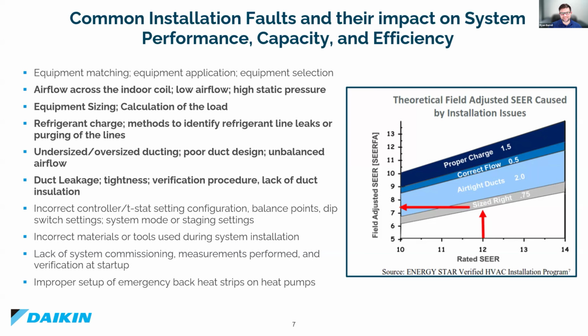But it's kind of that situation where they tell you to use UL 181 listed tape. Well, if you try to use UL 181 red letter tape in a 130-degree attic and you happen to sweat a lot like I do, then that stuff does not stick very well. It's a flex to sheet metal to anything. And so something like foil tape, which is what we don't want to use, happens to stick. So there are a lot of situations where you just have to understand that installers are doing the best with what they have, and they have no intent. They didn't wake up that morning to do something wrong, and if anything, it might just be a lack of information. So I put all these common installation faults. I don't mean to bash installers or anything like that, but this is a reality.